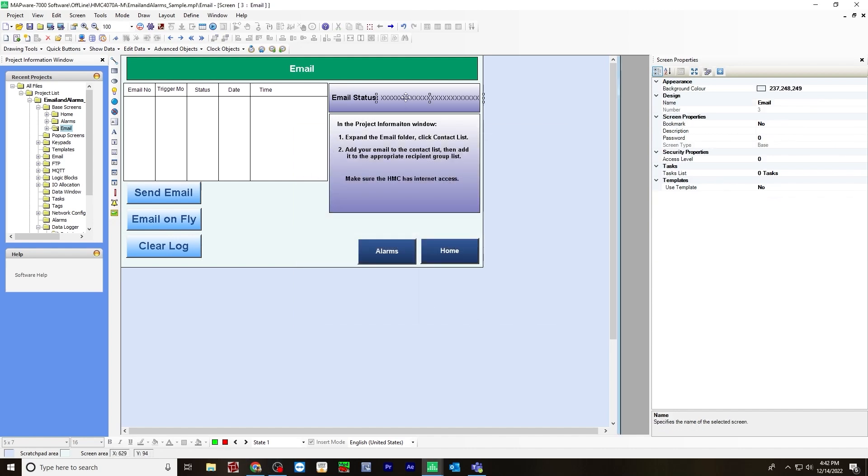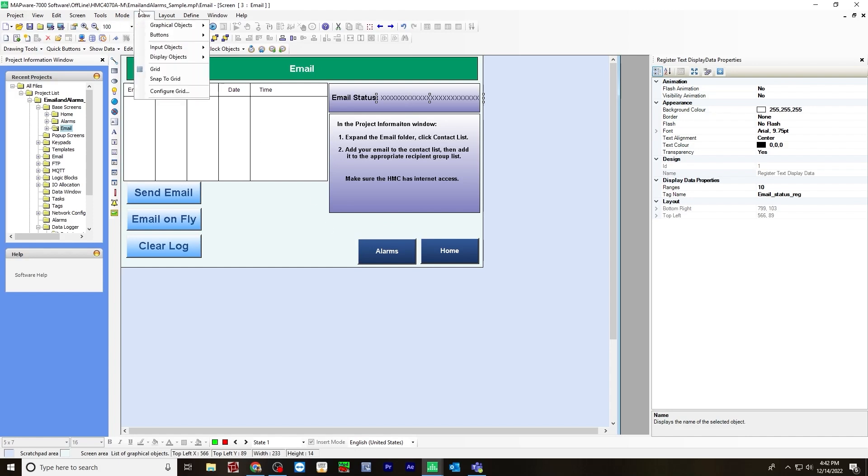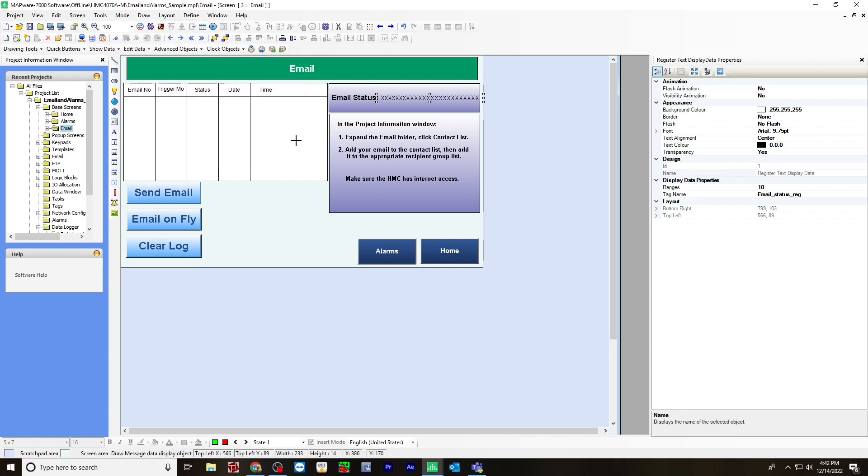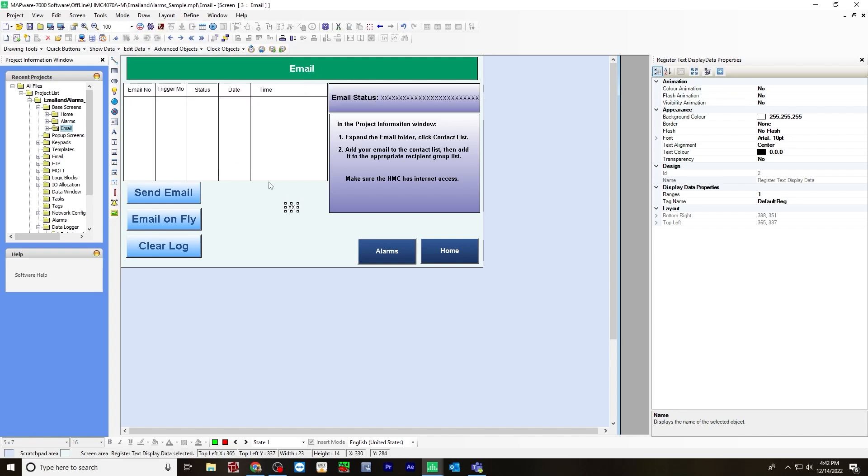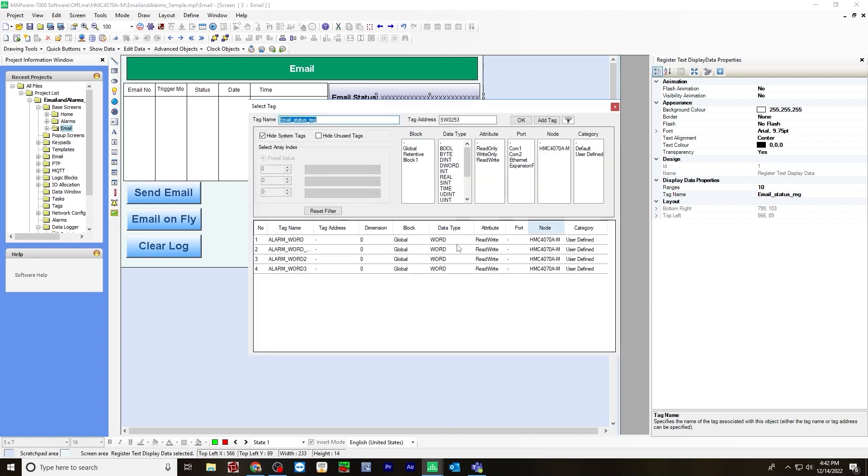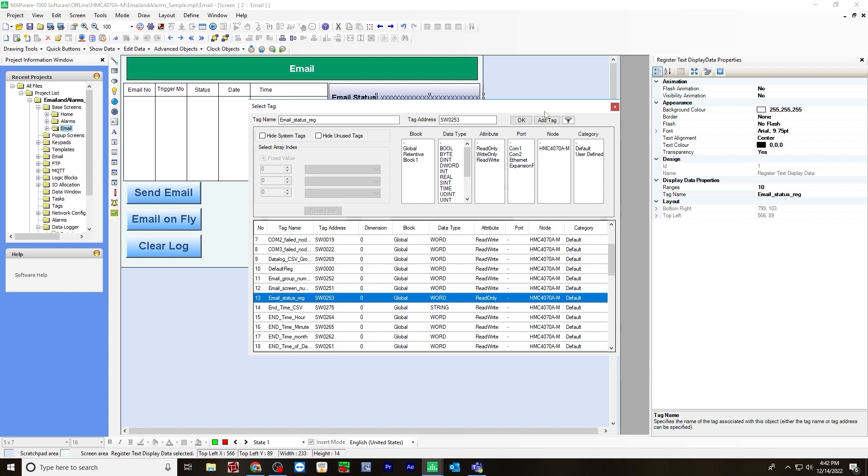Now the email status is a text display. You do that by going to draw display objects, data display, and then message display. And you drop it there. Now for the tag name for the message display, will be the email status register. So in your system registers, you search for email status register right here, and hit OK.